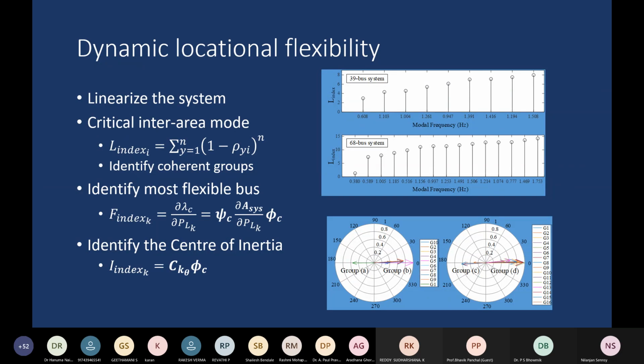Once we calculate the eigenvalues, they give the principal modes of oscillation. Then we look at how many generators participate in these modes of oscillation, and based on that, we calculate which mode is widely distributed and which mode is extremely localized. The extremely localized mode of oscillation is called a local mode, and the extremely distributed mode is called an inter-area mode of oscillation. Depending on the kind of mode, the stability property of that mode also comes out of this analysis. An inter-area mode is usually more critical compared to a localized mode, which means that if all the generators in the system are participating in a particular mode, then that mode is usually the most dominant and critical mode.